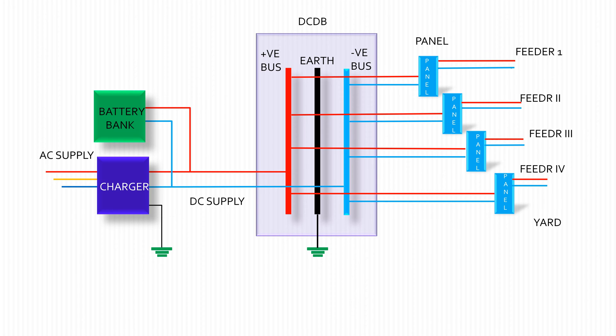The battery bank is connected with a charger and DC distribution board (DC DB). The DC DB comprises of a positive bus, negative bus, and earth or ground bus. From the DC DB, DC supply is sent to respective panels, and from panels to respective circuit breakers, isolators, transformers etc. by using LT cables.